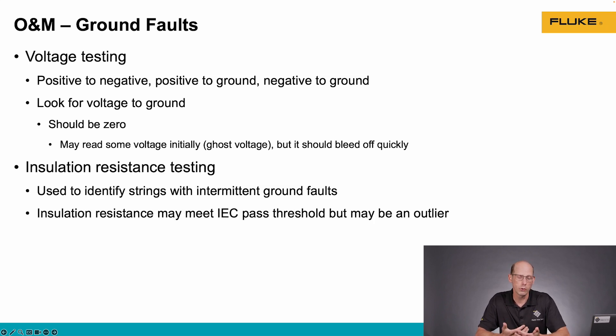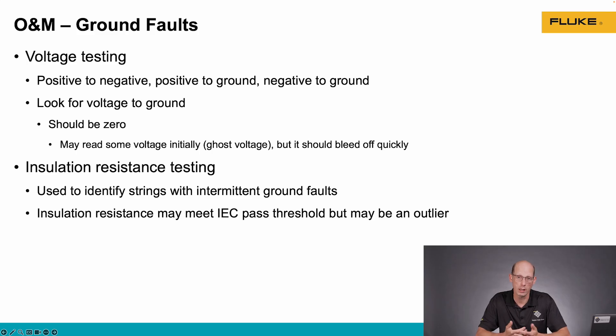We can also use insulation resistance testing to find circuits with ground faults. If we have a circuit with low insulation resistance values where we're leaking current to ground, that would be an indication that there's a ground fault on that circuit.